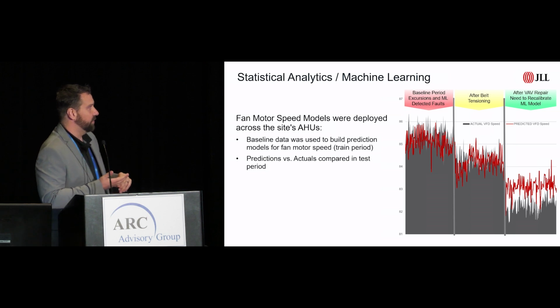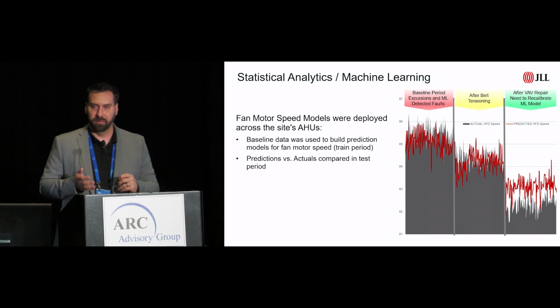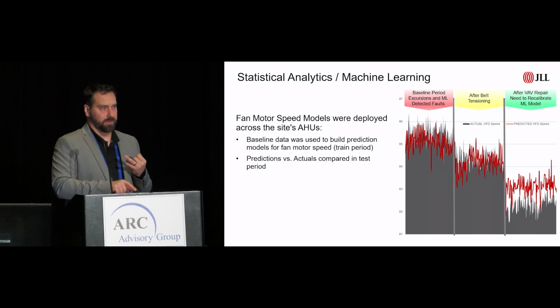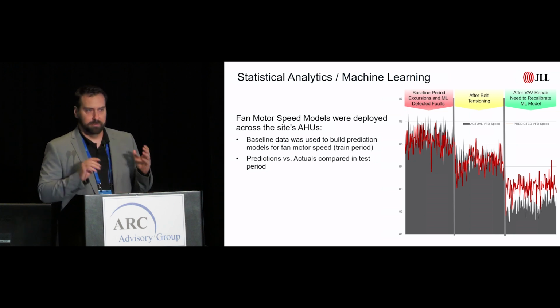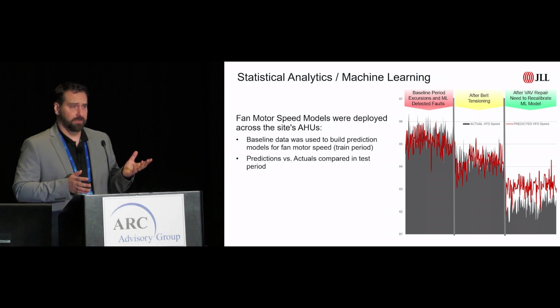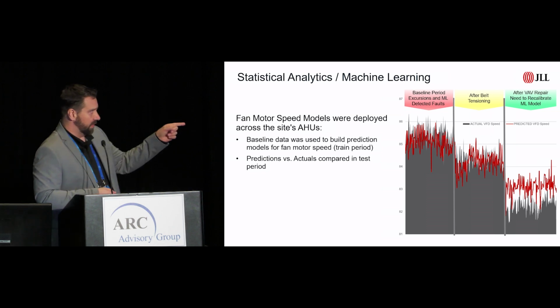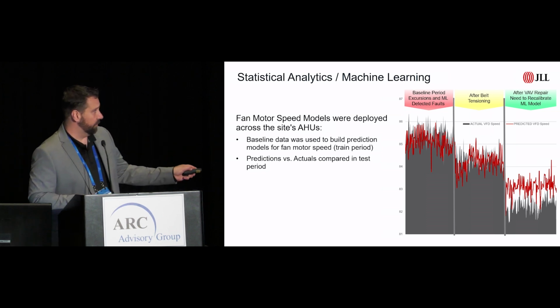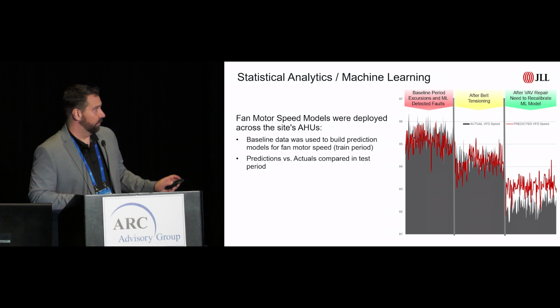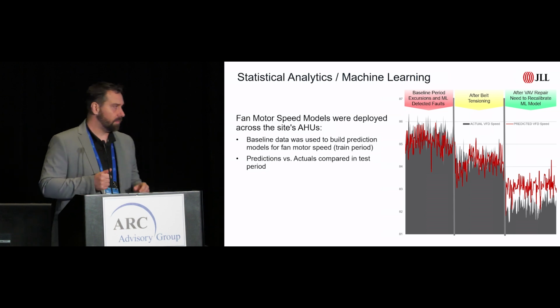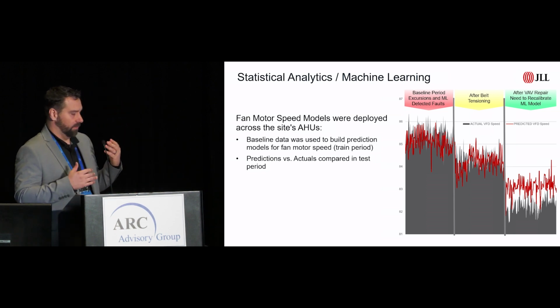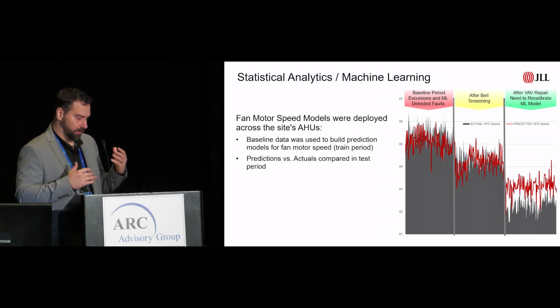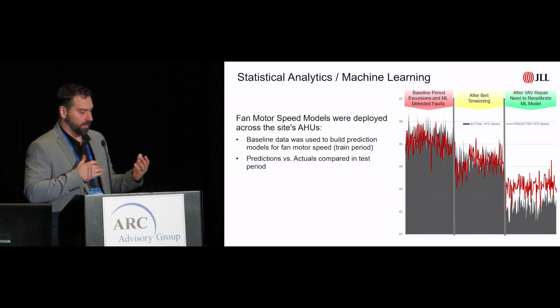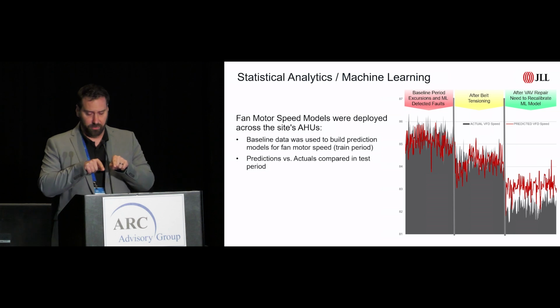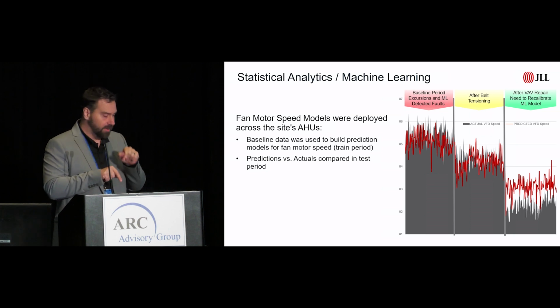When we're looking at the vibration data, we found there were some issues here. We found misalignment, belt slippage, tensioning issues. So after we did the basics of condition monitoring, you get to the yellow. Everything dropped down, right? We thought we were doing great. And then our IntelliCommand was starting to integrate and machine learn what was going on in the system around it. We were only focused on what that actual asset was doing, and not what the system was doing.